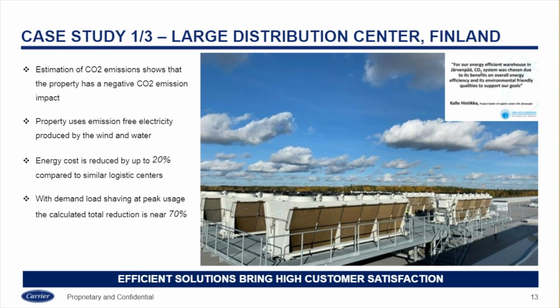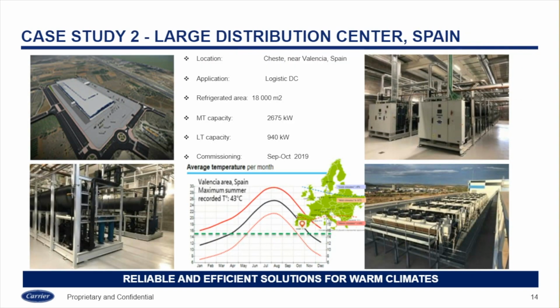Next page, please. The second case is another logistics center in Spain. The purpose here is to demonstrate the warm climate application for CO2 transcritical. This case is close to South Europe, in Valencia, Spain. The maximum ambient temperature in the summertime is close to 43 degrees.